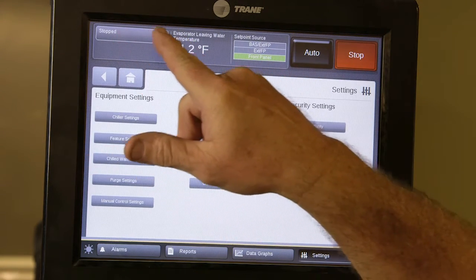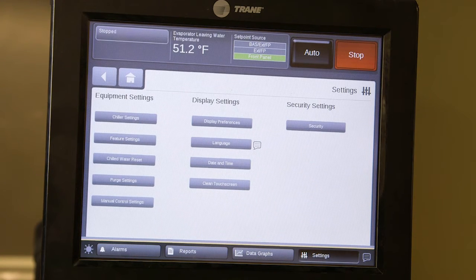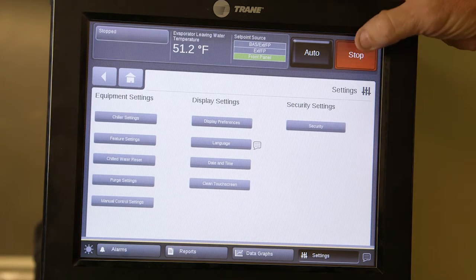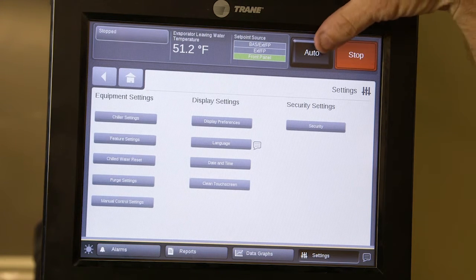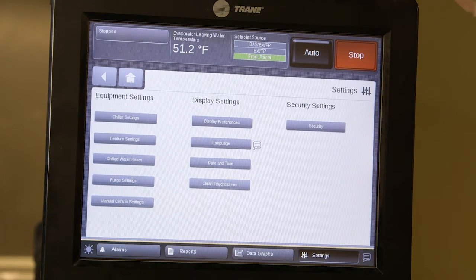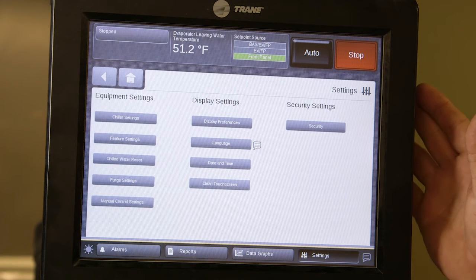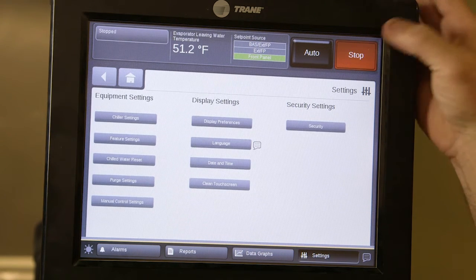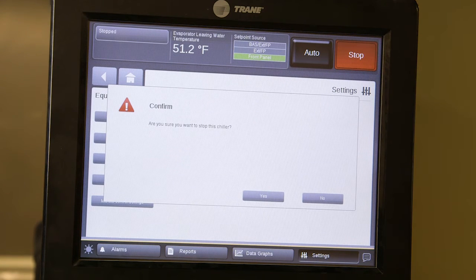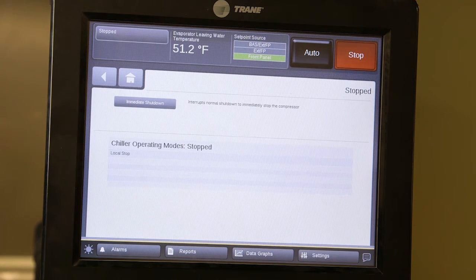The display at the top shows the chiller condition: running, stop, remote inhibit — where BAS controls put the chiller offline — and auto start and stop. Pressing the auto button initiates startup mode. If the chilled water pump and condenser water pump are running, it will start the oil pump, which runs for one to two minutes, and then the chiller will start once all safeties are proven and oil pressure is established. To stop the chiller, press the stop button — it will ask you to confirm, and once you hit yes the chiller mode is stopped.